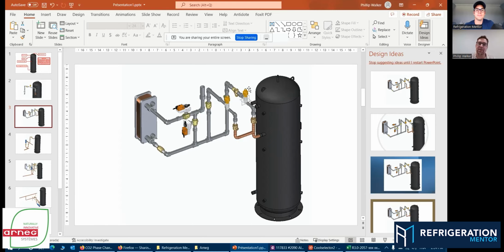We just spoke about this valve is the heart of the system. Well, it only makes sense to put a secondary valve in place. This is a dormant valve. That's why there's no strainer on it. All our systems have a secondary high pressure expansion valve, which in the event of failure, you unwire this valve, you pop the wire back on here, and the system's up and running while you source another valve. You just ball valve this line off right now, ball valve this line open, and the system is back and operational, and you're sourcing your valve.